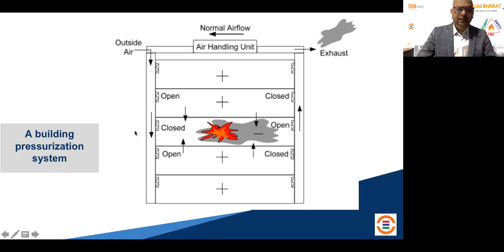Corridor. Now in hotels specifically, the corridor also needs to be pressurized because your lift well is pressurized, your lift lobby is pressurized, your stairway is pressurized. So you can't really keep your corridor naturally ventilated. It has to be pressurized. And specifically in high-rise hotels and buildings, you can't have natural ventilation. It has to be a temperature controlled lobby. In that case, pressurization is going to be very, very critical. Now, how do you do that? Again, it's a simple logic. Play with the dampers, play with the ventilation systems, create a positive pressure for the adjoining areas and negative pressure inside the area which is under fire.